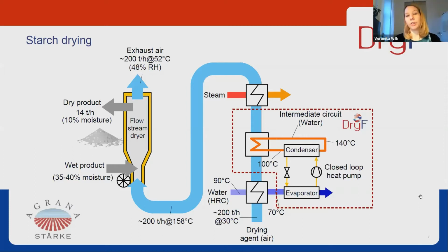Then we have the heat pump, the heat exchanger for the heat pump, and then there's a heat exchanger that is using steam to ensure that the final drying temperature is reached. And as the heat source for our heat pump, we use that hot water cycle that still has 70 degrees after the heat exchanger. And the heat pump is connected to the drying air with an intermediate cycle. And this is just to ensure that we can test different temperatures, that we can also measure different temperatures in that water cycle to really have a nice balance on the heat pump and check all the operation conditions.